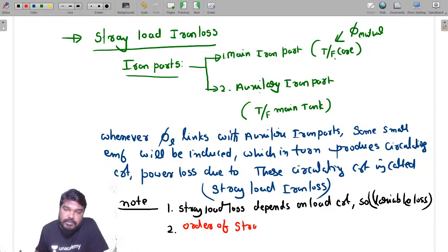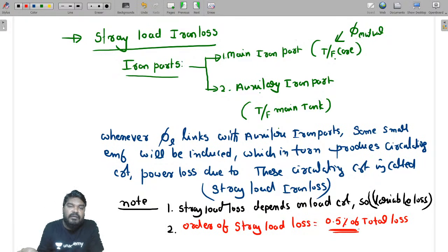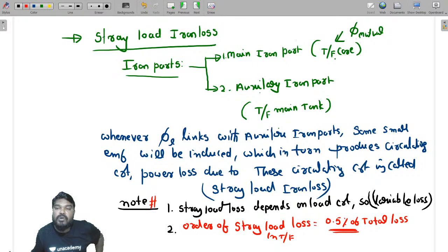So this is the order of stray load loss. This is equal to 0.5% of total loss. That's why it is treated as the minor losses of the transformer. These are the two important notes. One is stray load loss depends on the load current, so it is treated as variable losses. And the order of the stray load loss in the transformer is equal to 0.5% of the total loss. Okay, clear?